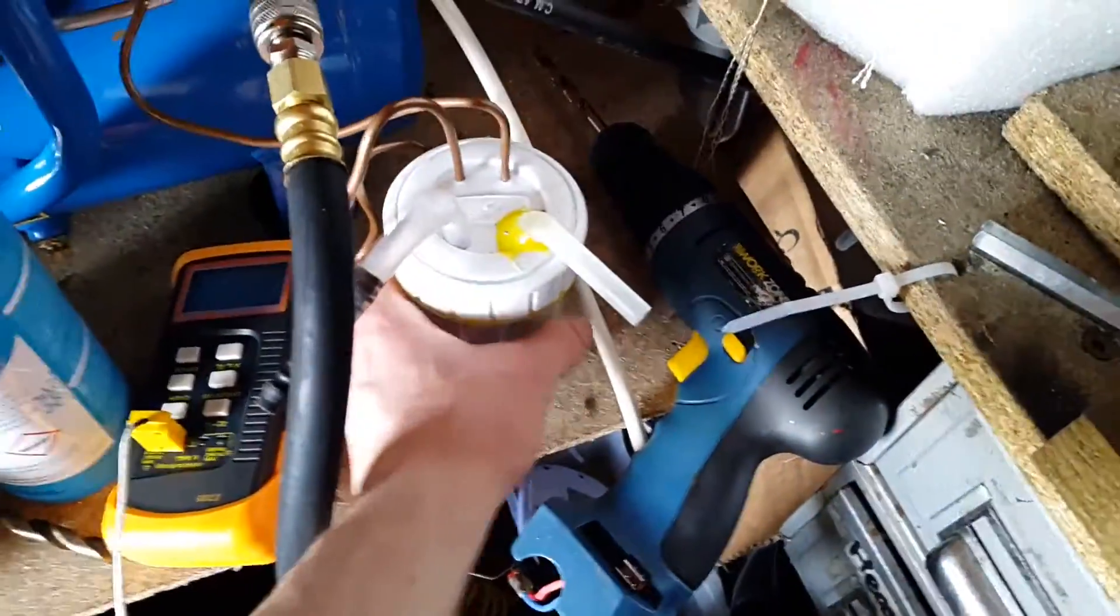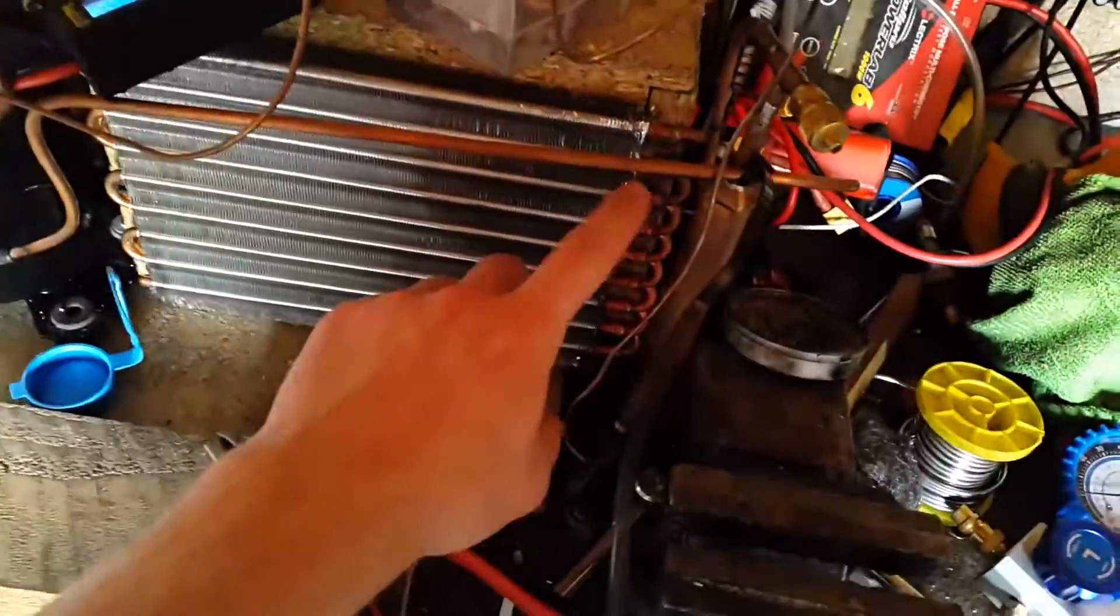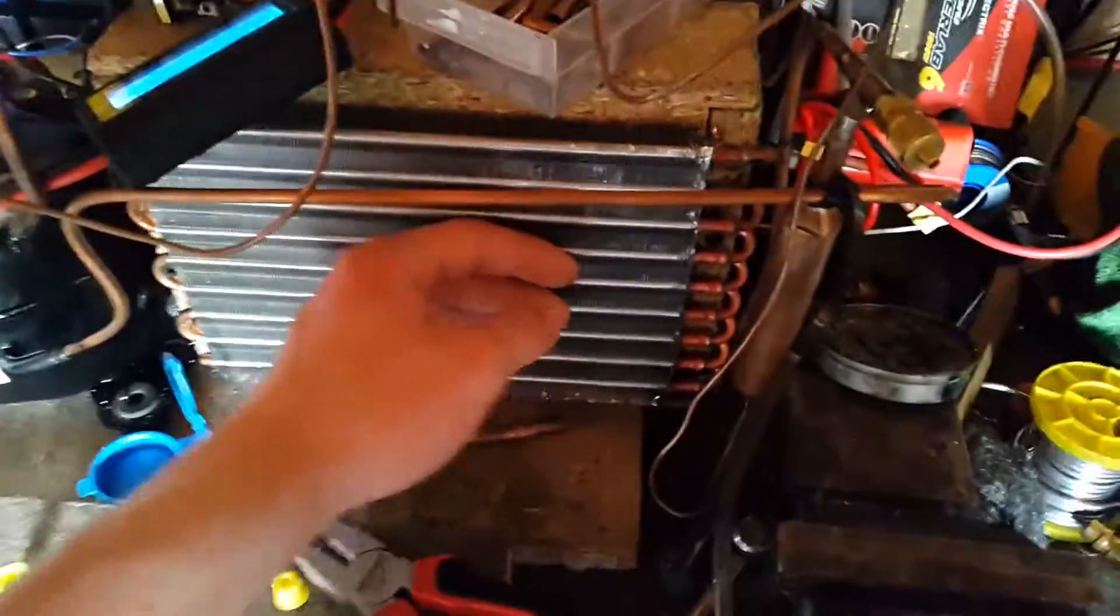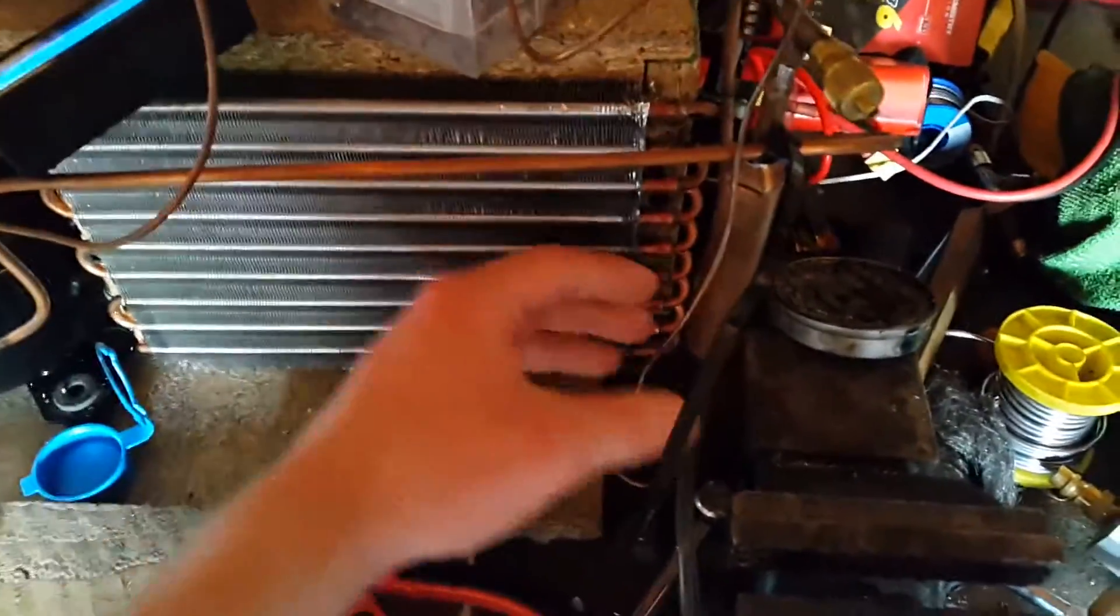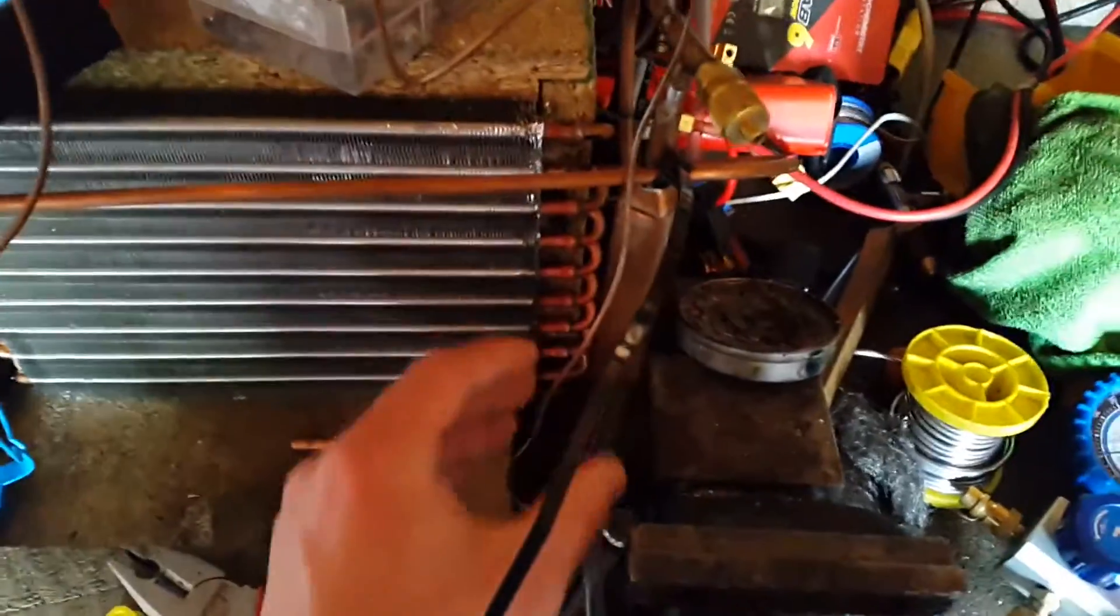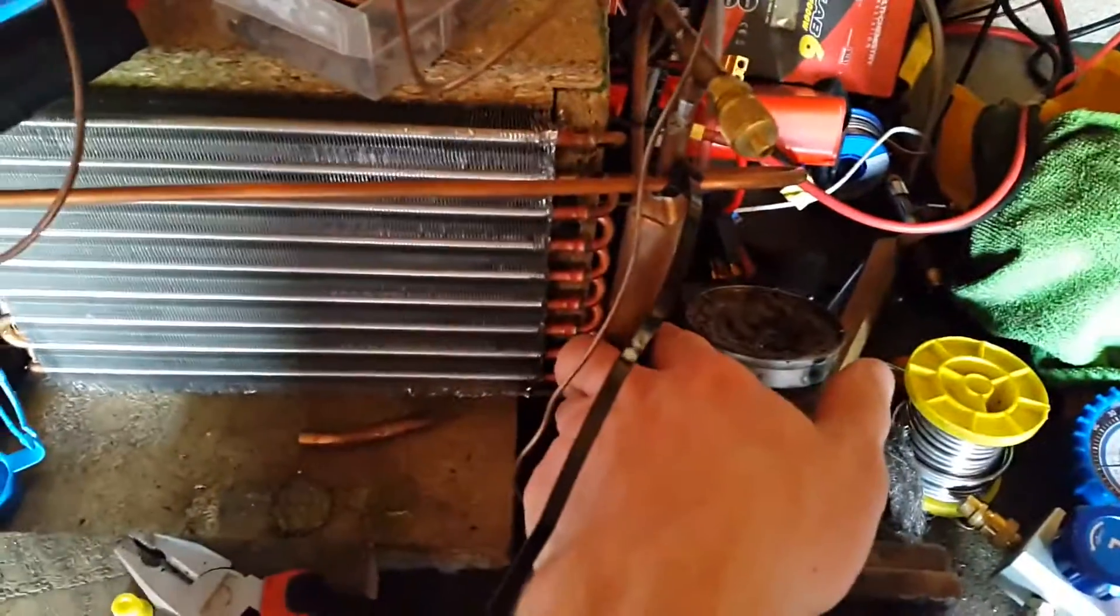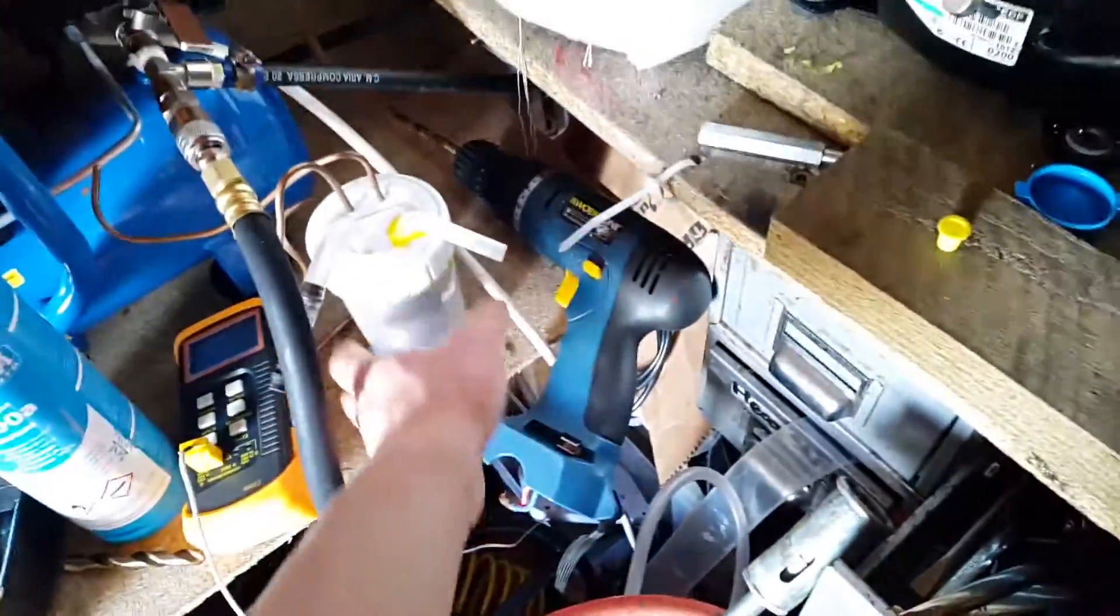The liquid-cooled condenser is sitting here. It uses 4 millimeter copper tubing, but the tubing size inside this condenser is 5 millimeter. I've noticed that using this condenser, the liquid coming back in the filter dryer is much cooler than using the liquid-cooled one. Something because of heat transfer inefficiency, and it's working a lot better now.